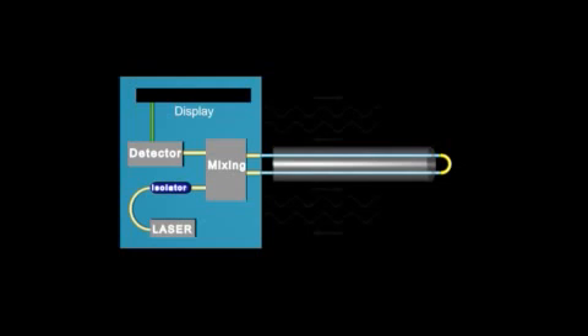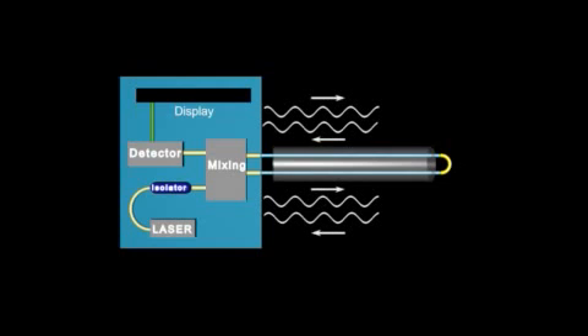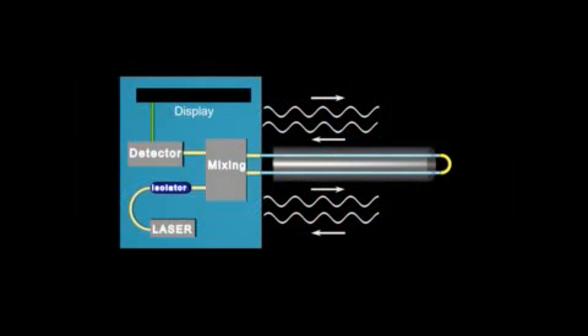The optical mixing module ensures that light from the laser travels in both directions around the fiber loop, forming an interferometer. Because laser energy is coherent, splitting the laser light into a pair of beams and allowing them to interact over a long fiber span produces a pattern of interference in the fibers. If the light were visible, this interference pattern would show up as a series of brighter and darker regions along the fiber span. The interference pattern also returns to the optical module, where it is monitored by a detector system.